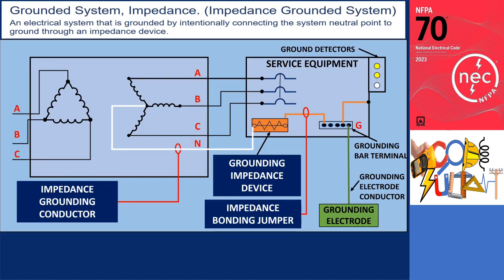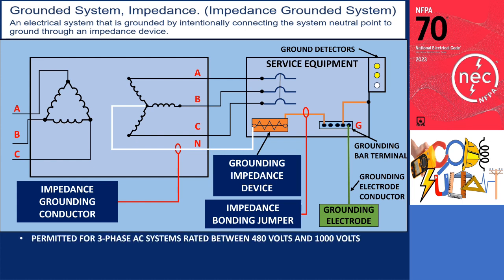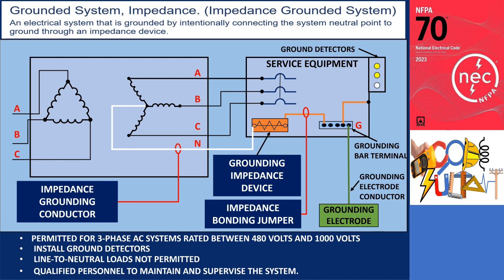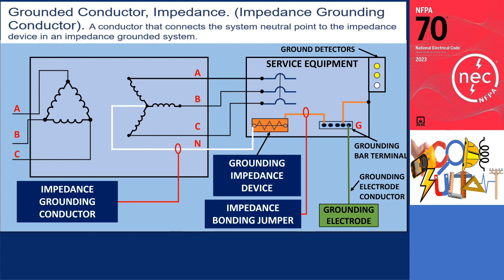An impedance grounded system refers to an electrical system where the system's neutral point is intentionally connected to the ground through an impedance device, typically referred to as a high impedance grounded neutral system. The illustration showcases a typical connection of an impedance grounded system where the neutral point is linked to the ground through an impedance device. This system is only permitted for three-phase AC systems rated between 480 volts and 1000 volts. Additionally, specific conditions must be met, including the installation of ground detectors, the prohibition of line-to-neutral loads, and the requirement for qualified personnel to maintain and supervise the system. The impedance grounding conductor is defined as a conductor that connects the system's neutral point to the impedance device in an impedance grounded system.